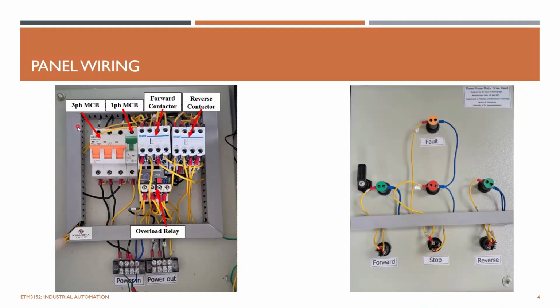Now you can see this panel wiring. Here, the main power comes in, three-phase power comes in, and that is wired to these terminals along with the protective earth. The main power goes out from the power out, which is connected to the three-phase induction motor along with the protective earth. So the protective earth or the chassis of the motor comes here, and the panel chassis is also connected to the protective earth, which all goes to the protective earth of your panel wiring at the installation.